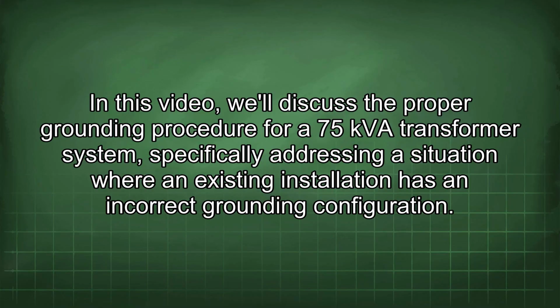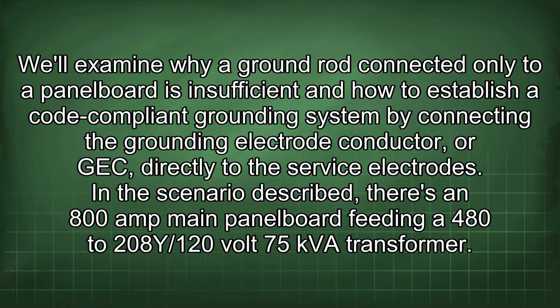In this video, we'll discuss the proper grounding procedure for a 75 kVA transformer system, specifically addressing a situation where an existing installation has an incorrect grounding configuration. We'll examine why a ground rod connected only to a panel board is insufficient and how to establish a code-compliant grounding system by connecting the grounding electrode conductor, or GEC, directly to the service electrodes.